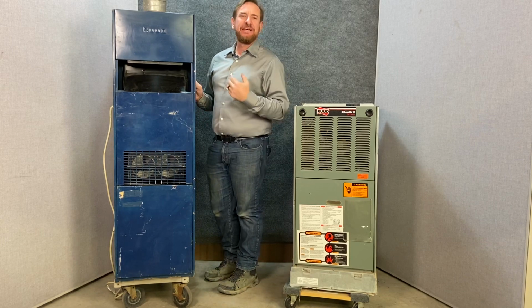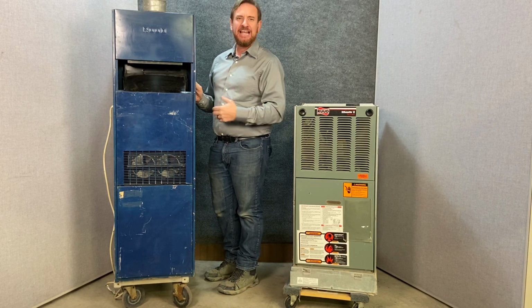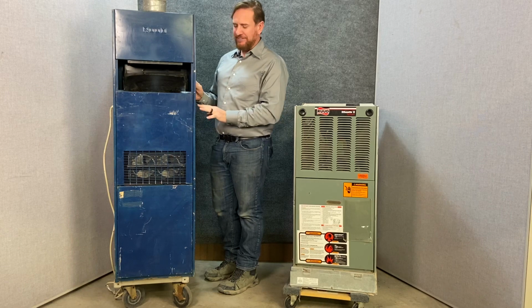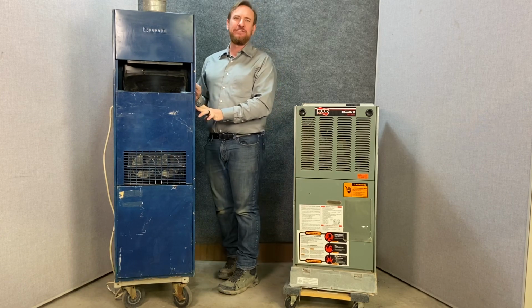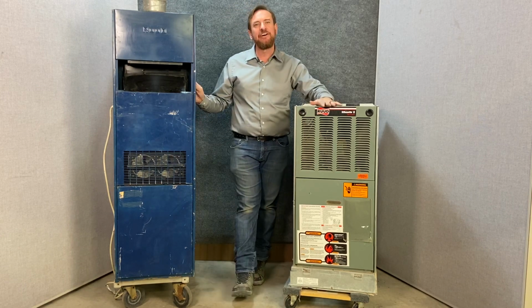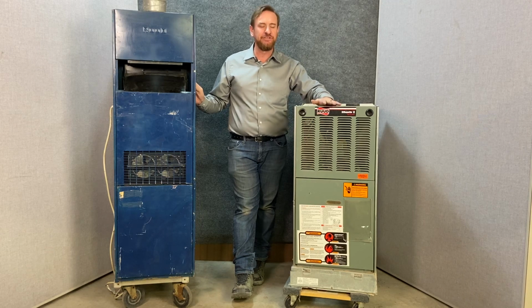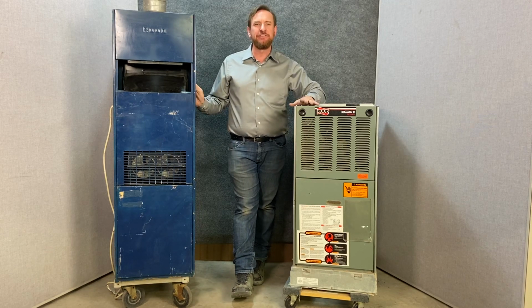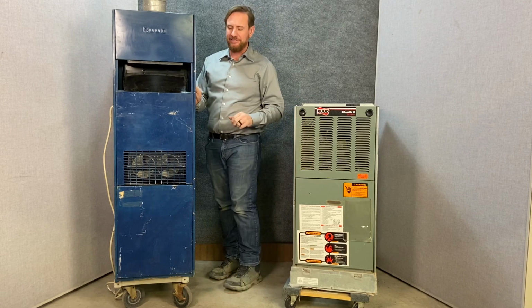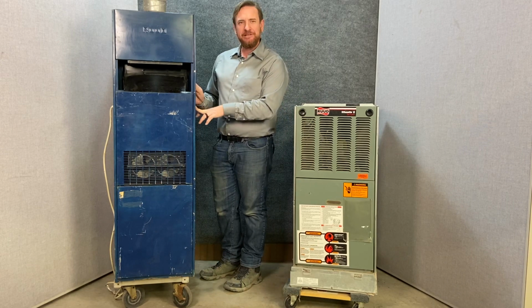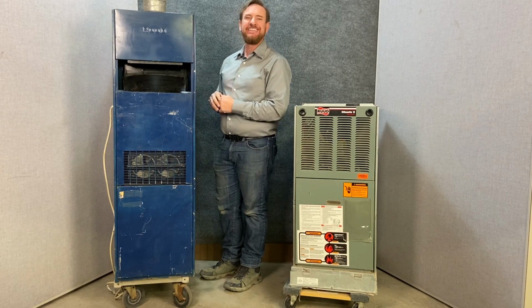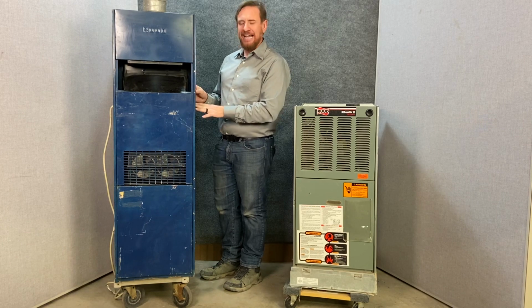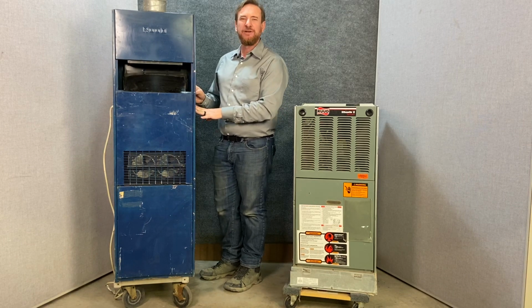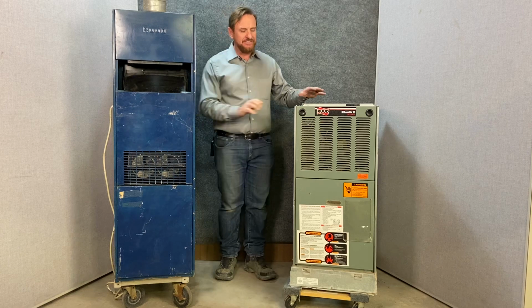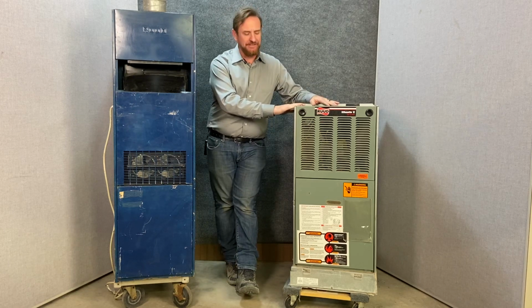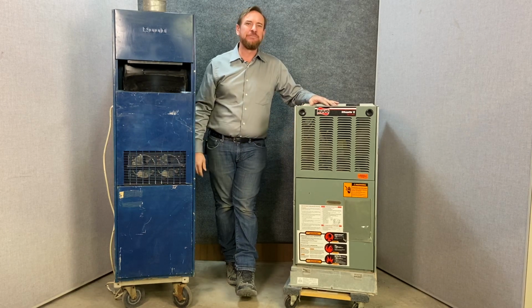They rate furnaces by the input BTUs, so taking the gas, converting it to input. So this furnace had an input of 80,000 BTUs, and this had an input slightly smaller at 75,000 BTUs. There's only a 5,000 BTU difference, but let's go into a little bit more detail. This furnace is 80,000 BTUs input. It's only using 60% of that to heat the house. So the actual heating content of this furnace is 48,000 BTUs. Since this furnace is an 80% furnace, we're actually getting 60,000 BTUs of heat.